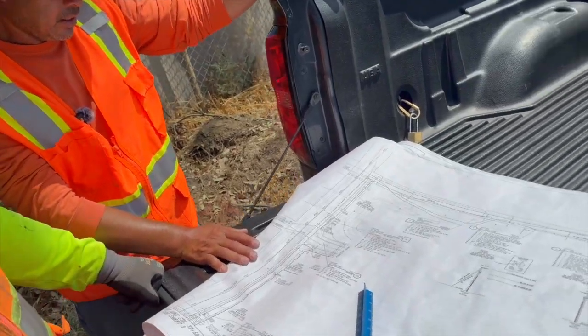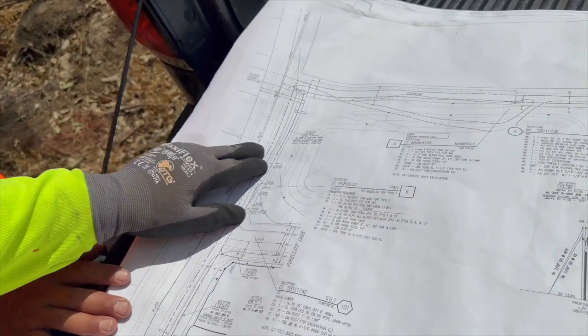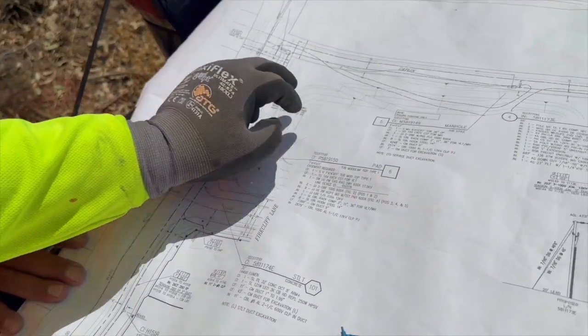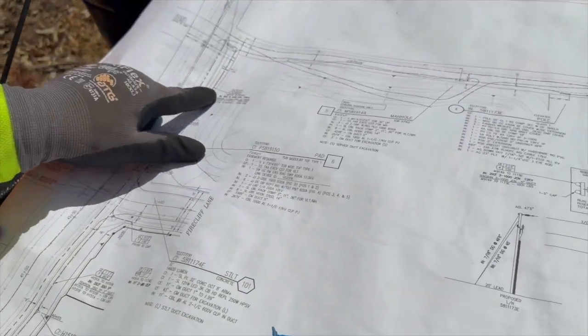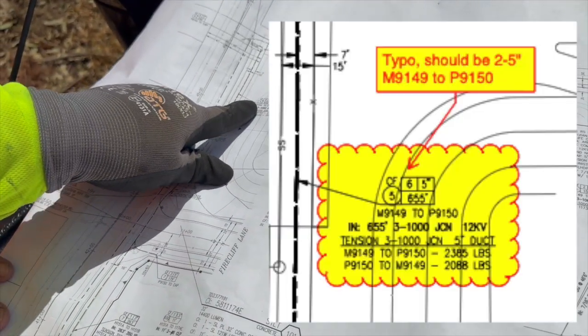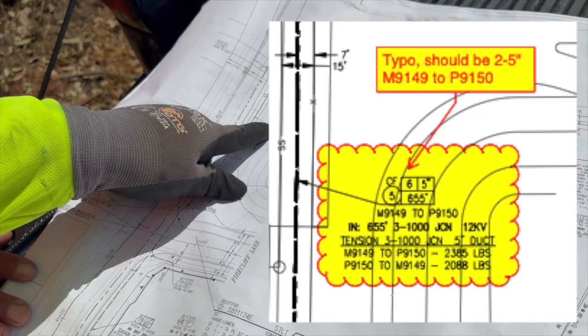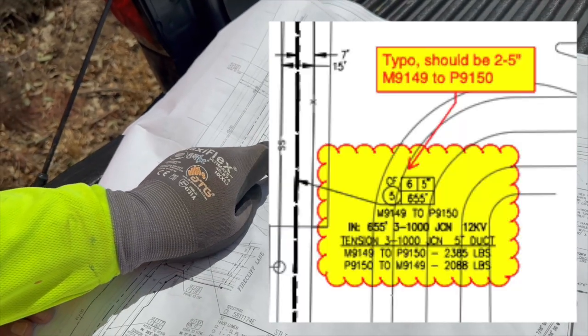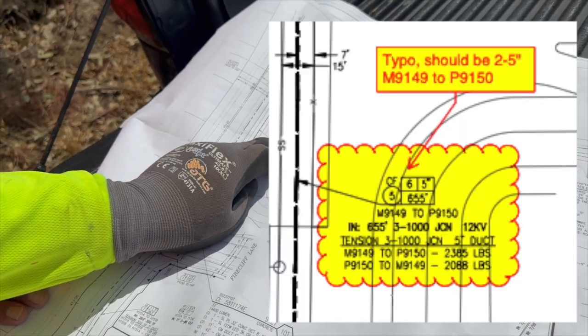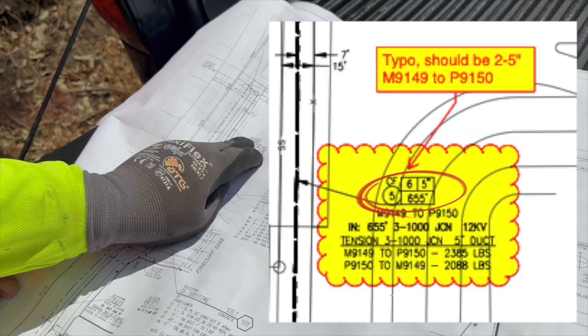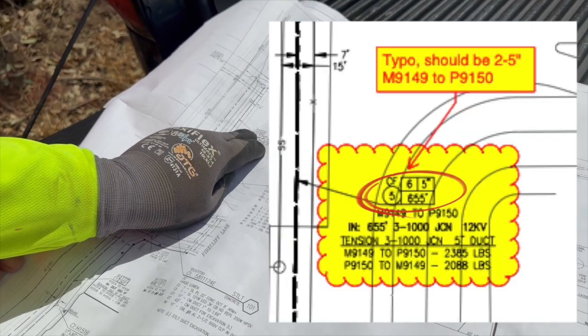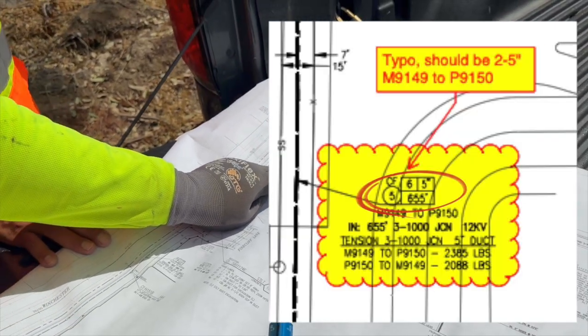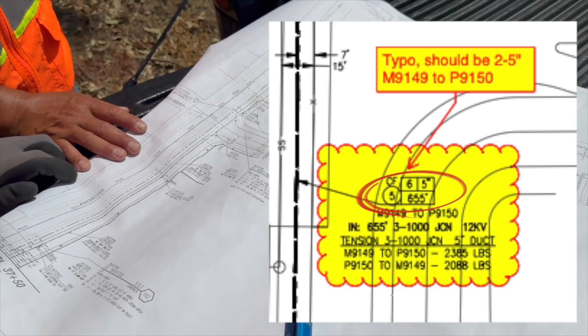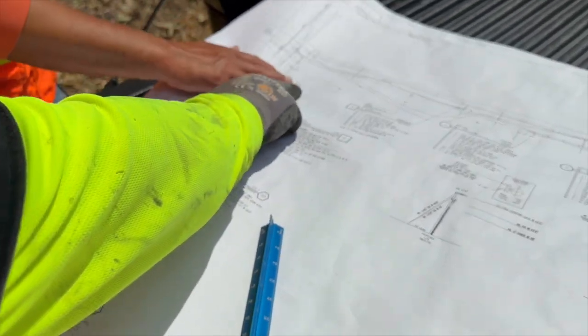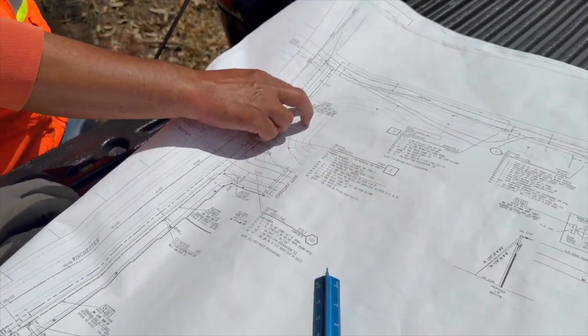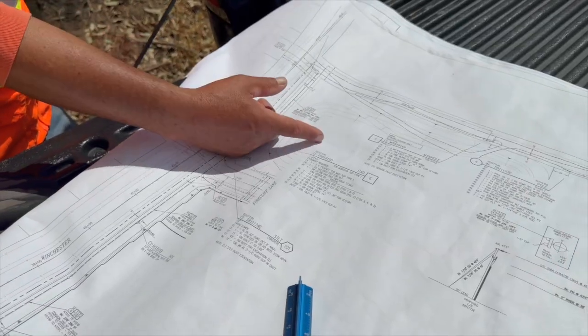Now I see different notes right here. What does this one mean for you, Manny? This one is telling me from one structure to the other. It's showing you how many conduits are going from one structure to another. Like here, on call out number 5, it shows six 5-inch conduits, 655 feet from one box to another. So that gives you the distance from the manhole.